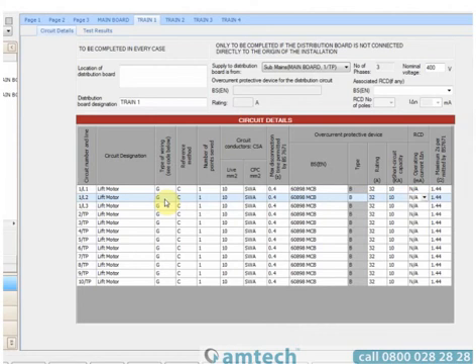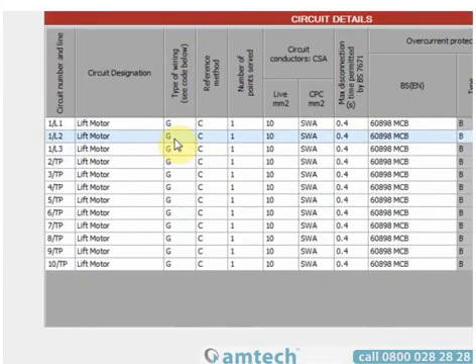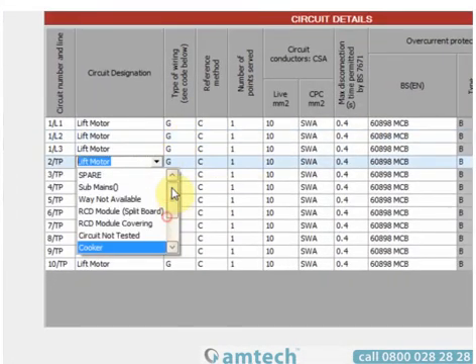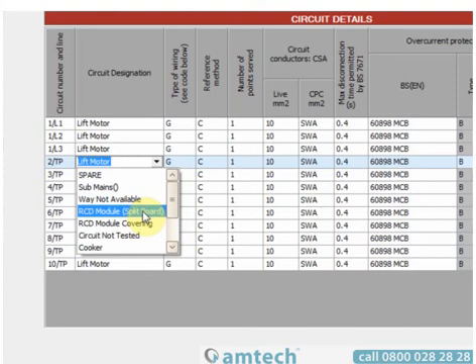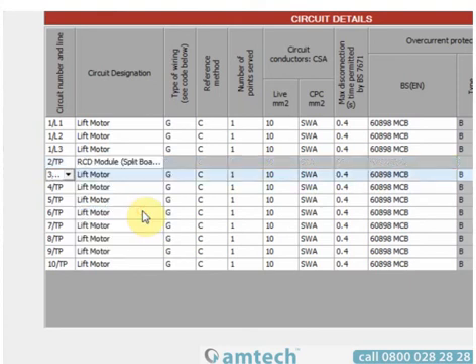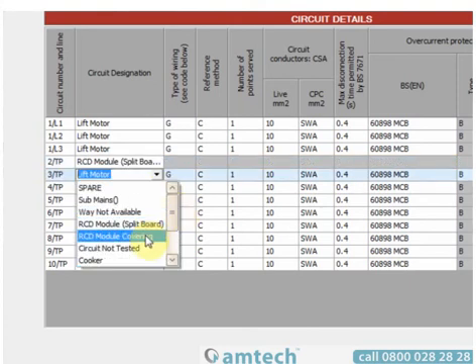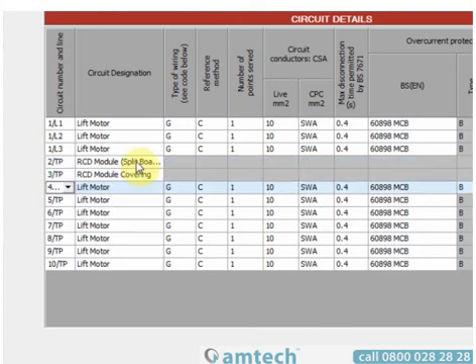Other things worth mentioning in the circuit details are in the drop-downs, which contain some pre-entered values. Things like 'Way Not Available' means that although the way is there, you physically can't connect a circuit to it — this could be because of an oversized device or a broken terminal. You also have the option of 'RCD Module Split Board' and 'RCD Module Covering', which indicates that these ways are taken up by an RCD.